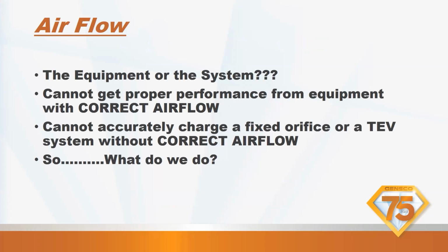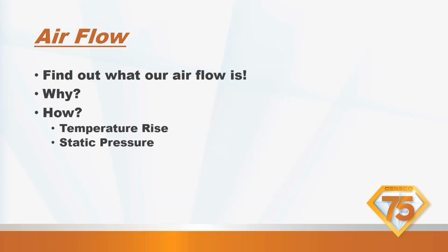Is it the equipment or the system? You cannot get the proper performance from the equipment without the correct airflow, and you cannot accurately charge the fixed orifice or TXV system without the correct airflow. So what do we do? We find out what our airflow is. We need to know what our CFMs per ton are through the equipment so that we can see if it's within 10% of the listed rating in the AHRI. 400 CFMs per ton for heat pumps is normal. 325 to 350 for an AC is normal.